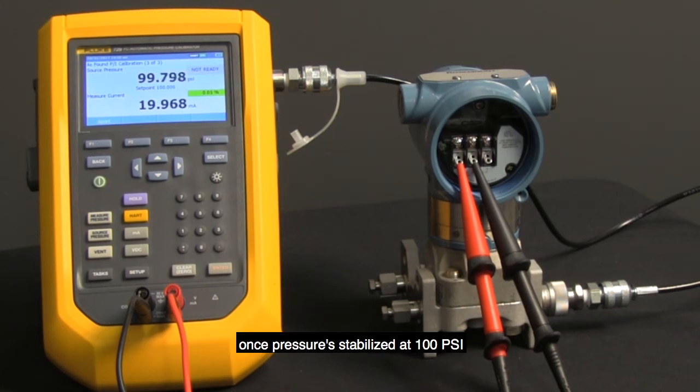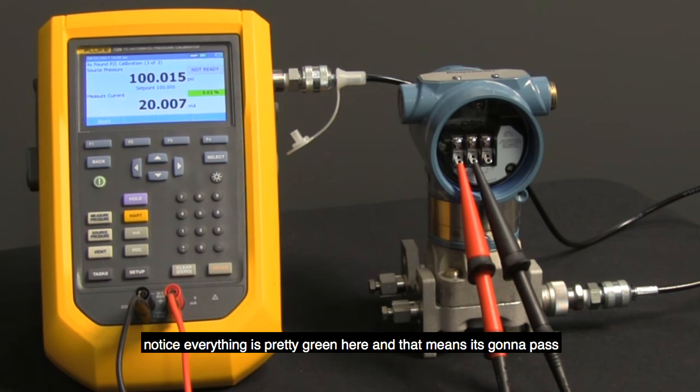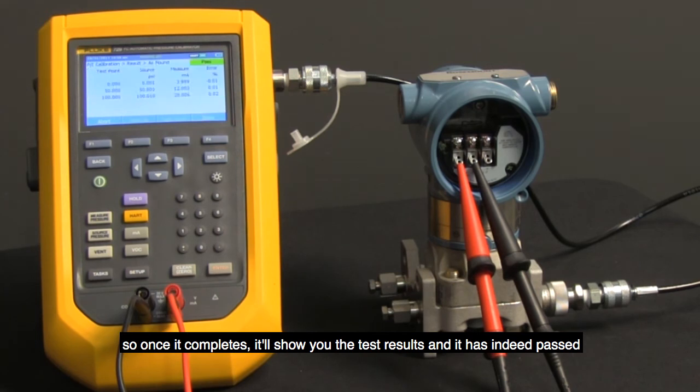Once pressure is stabilized at 100 PSI, the 729 will document the 4-20 output. And you'll notice everything is pretty green here, and that means it's going to pass. So once it completes, it'll show you the test results, and it has indeed passed.